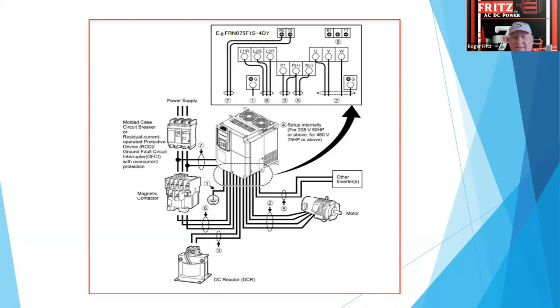And then they show the power supply with a circuit breaker. We highly recommend that when you put it in, you definitely use a fast-acting circuit breaker to protect diodes and transistors, or put in fast-reacting fuses. I've seen a lot of real high spikes that end up going in and damaging the inverter. These are not inexpensive devices, so it's much easier to change a fuse. So you need that response here, and we put fast-acting fuses in the panels that we build.